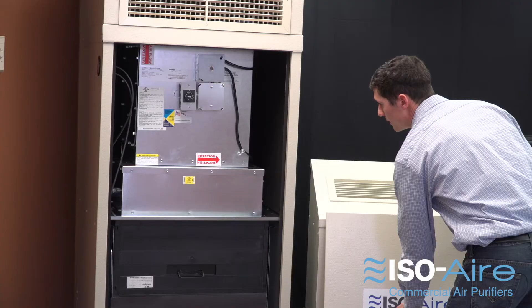Do this every 2 to 3 months, and we actually have a new extended life filter that you can get as well that has double the lifespan. The pre-filter is very important because it helps extend the life of the HEPA filter, which is here. To change out the HEPA filter, it's pretty easy across our units. We use securing bolts to secure the gasket for a proper seal. Simply loosen those, the HEPA filter should drop down, change it out, slide the new one in, tighten back up, and you're good to go. Again, that HEPA filter is 3 to 5 year lifespan. We even have gauges on the side of the units so you can see the static pressure so you know when it's time to service the filter. Then when you're done, simply slide it back on and you're good to go.